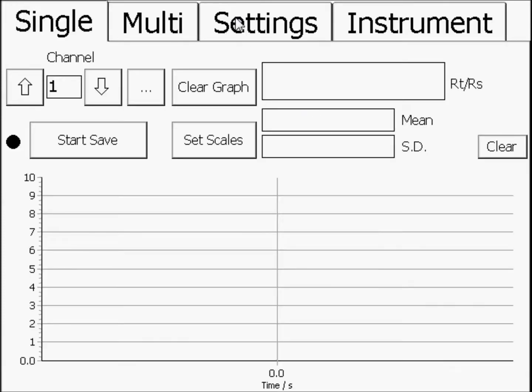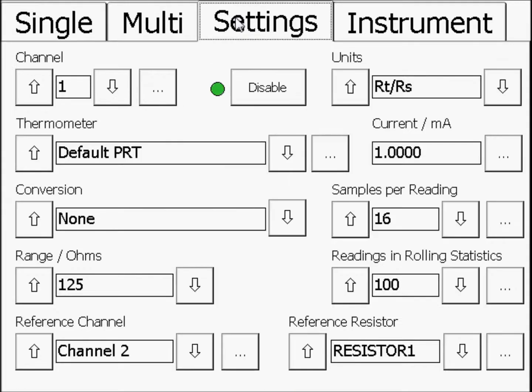Before making a measurement, make sure the reference resistor you are using is saved in the micro-K's database, and connect the SPRT you are using to channel 1 and the reference resistor to channel 2.